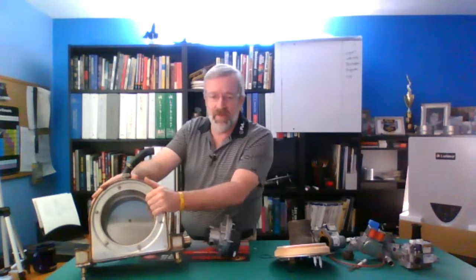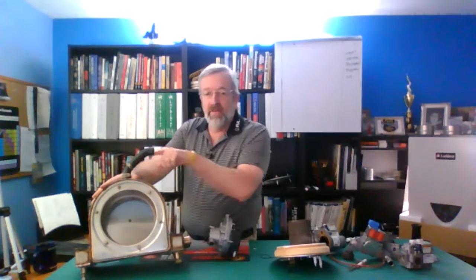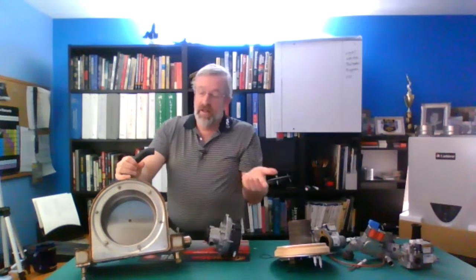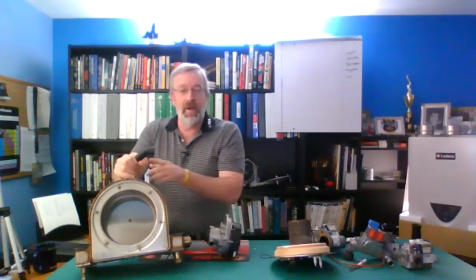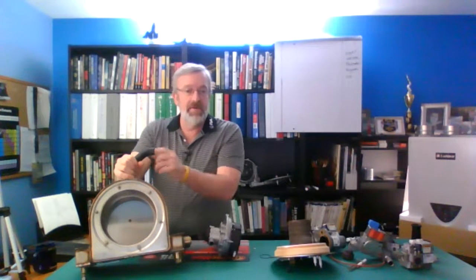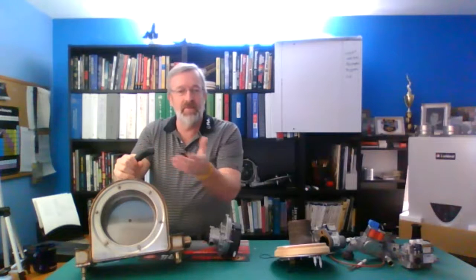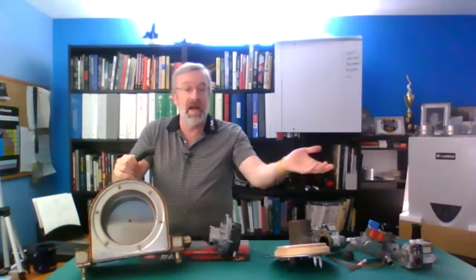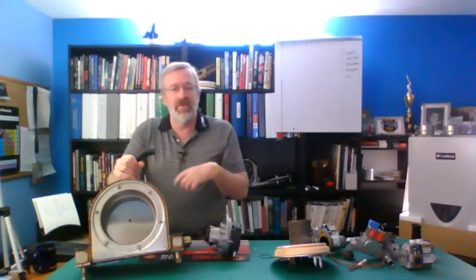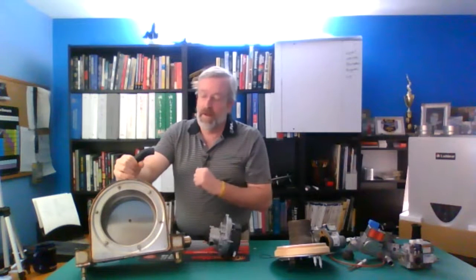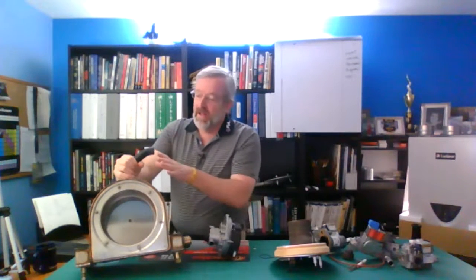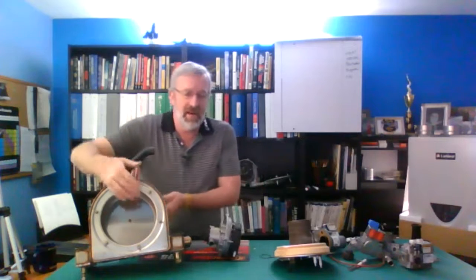Now, for simplicity, this one's upside down. Flush it down. It's going to come out through here into my condensate. A couple of creative guys that I've seen have put a barb by hose adapter on. So they disconnect this off, put a barb by hose adapter on, and you're able to put it onto a hose and flush it right out of the boiler, not through the condensate trap. If you do flush through the condensate trap, make sure you're taking that trap off and cleaning it before you put the boiler back in service. The 5-to-1 style had an actual kind of cylinder trap in there, whereas the new fire tube just has a little trap on the bottom, and you can pull that trap right off and clean it out nice and easy.